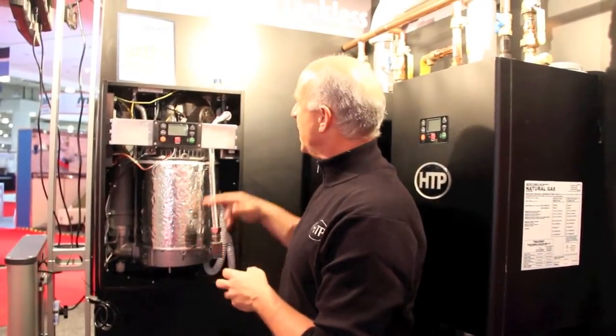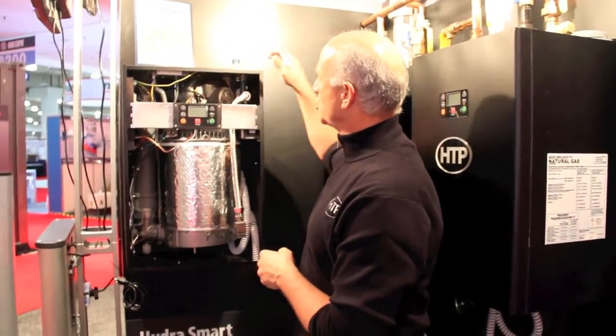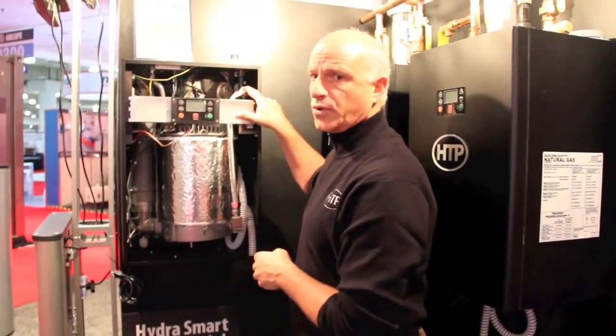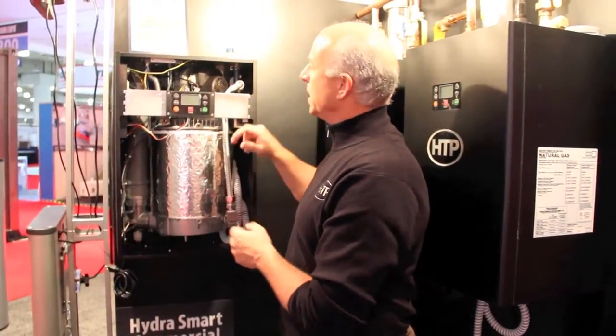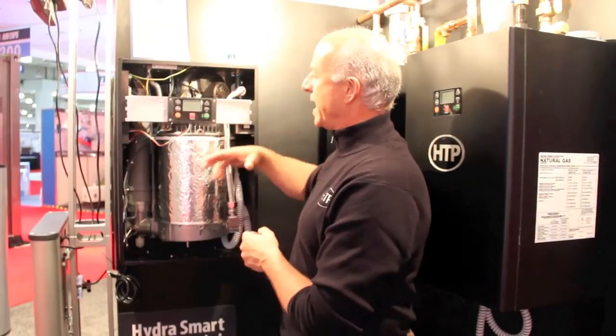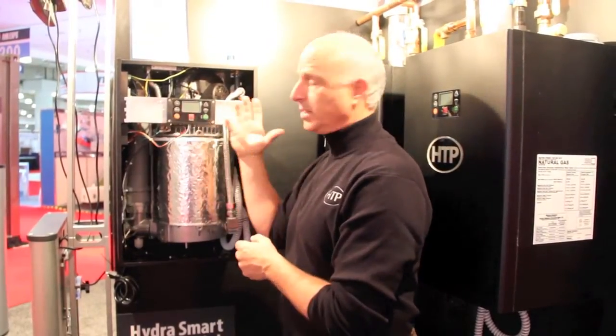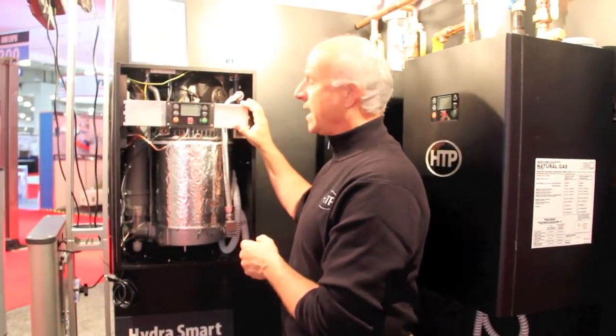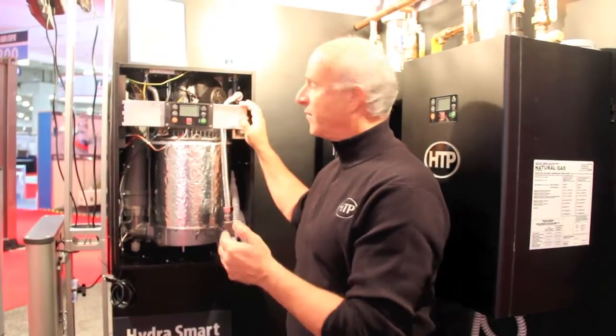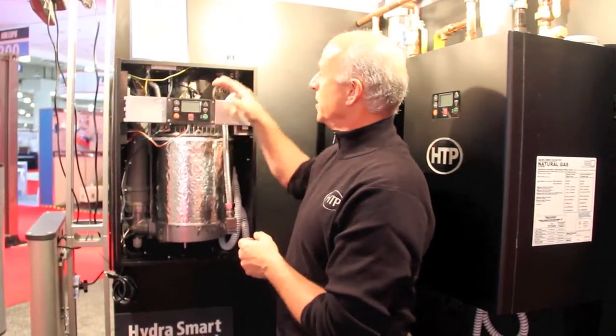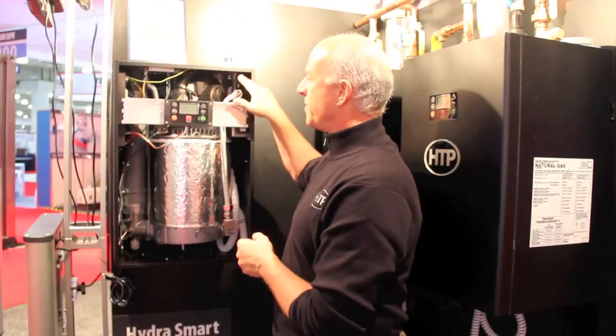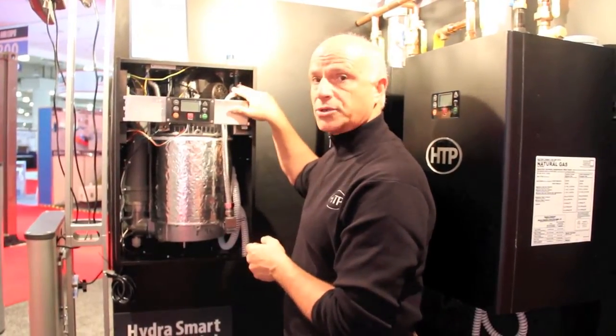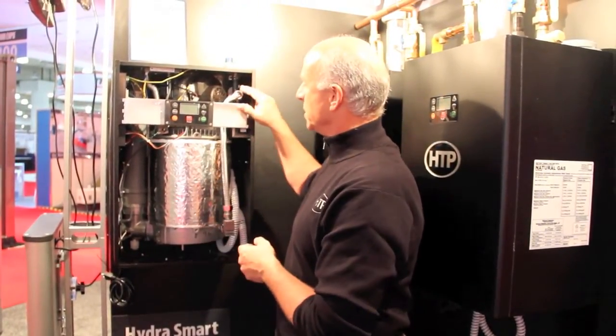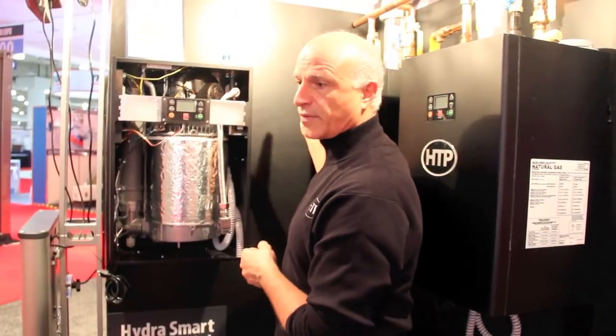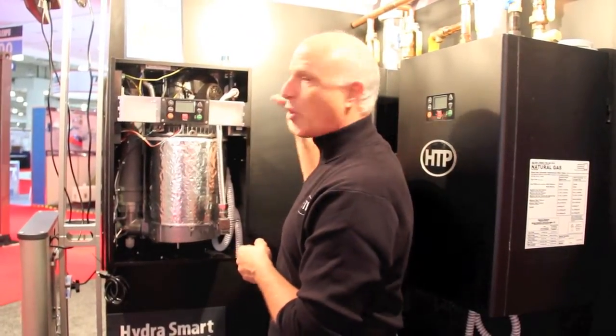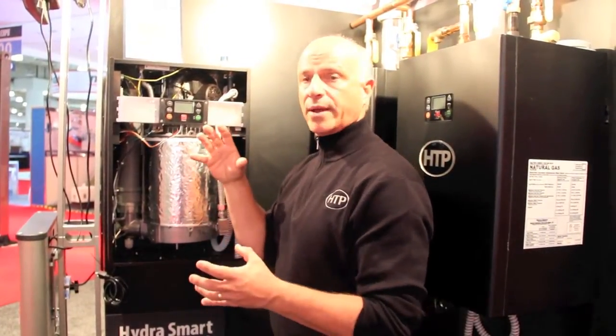It has valves. This valve over here will shut the water flow down if you have multiples, and it only opens up, so if we have a bank of these and we're running a cascade system where we have 3 or 4, what will happen is the water flow will go through the master, go through the first heat exchanger. As the flow increases, we isolate, we shut off the flow on the other units, and then we open them up as we see more demand.